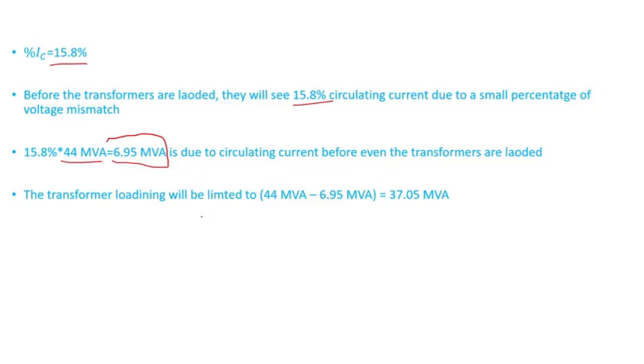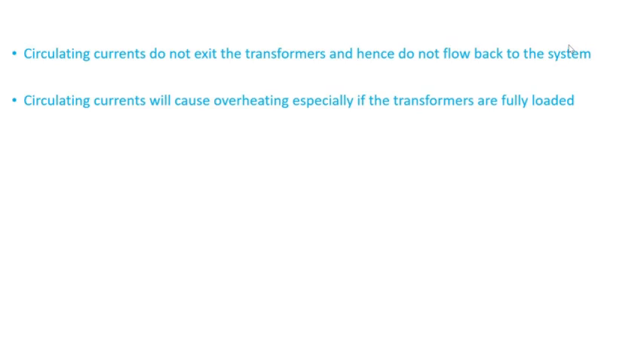This means transformer loading is limited — the combined capacity is 44 MVA, but you must subtract the capacity consumed by circulating current. The circulating currents do not exit the transformers or return to the system; they stay trapped within the transformer loop, flowing from the high side through the low side and back.